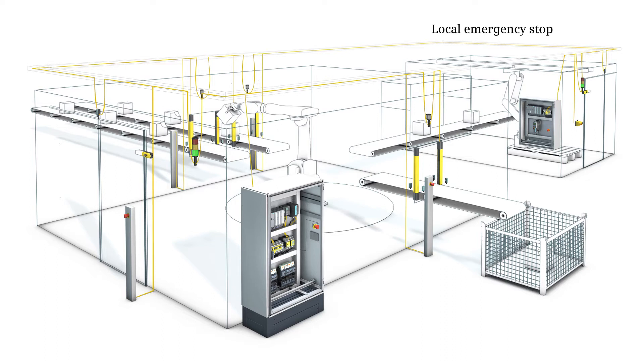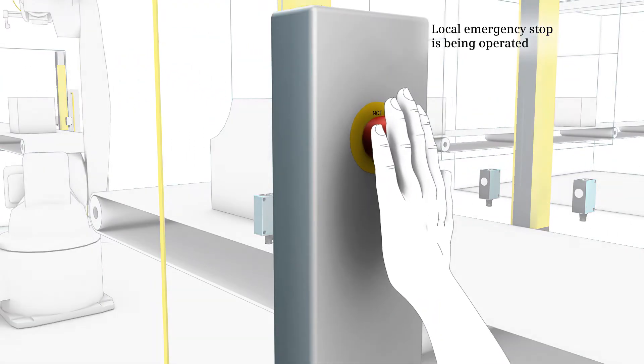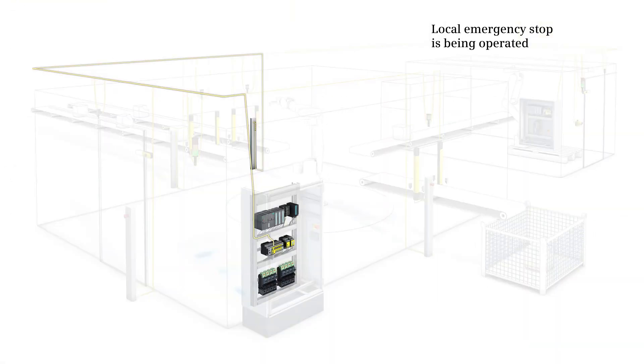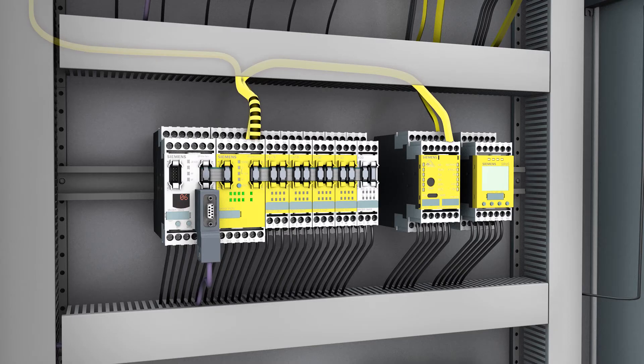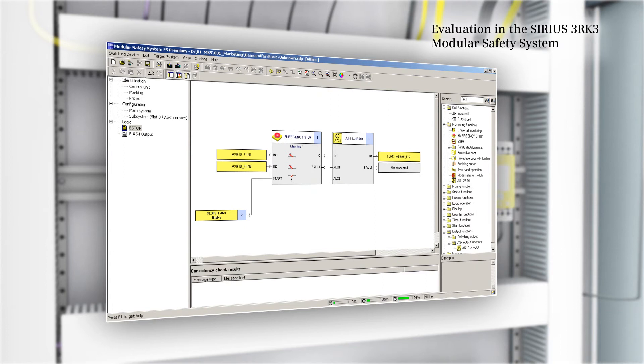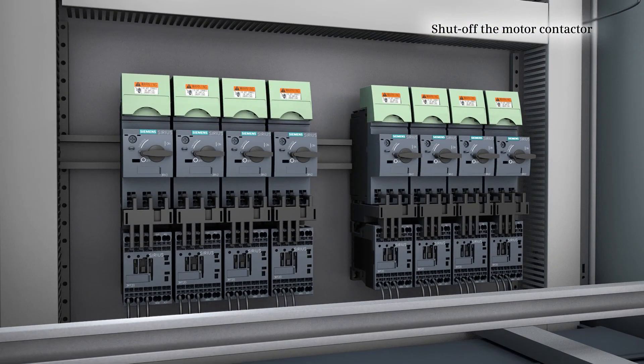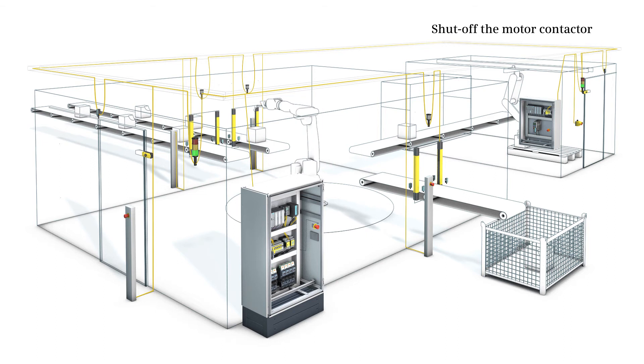Example: Emergency Stop. If the local emergency stop is operated on the parcel feed conveyor of our example plant, the stop signal is read into the 3RK3 modular safety system via ASI. The system evaluates the signal and then transmits the shutdown command onto the assigned safe ASI output. This opens the motor contactors and immediately shuts down the motors of the two parcel feed conveyors and the robot.